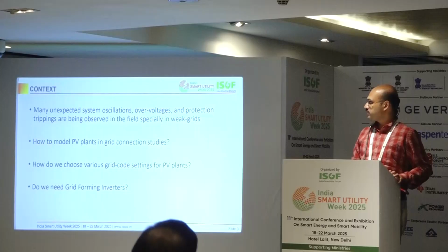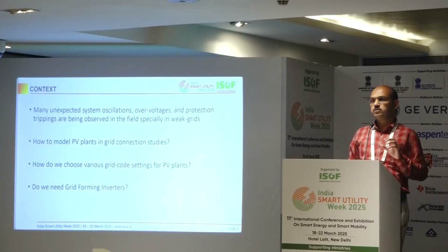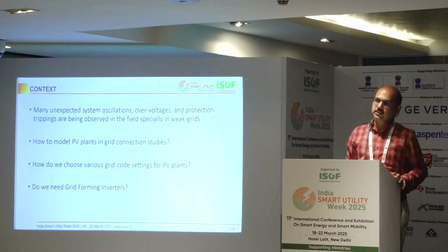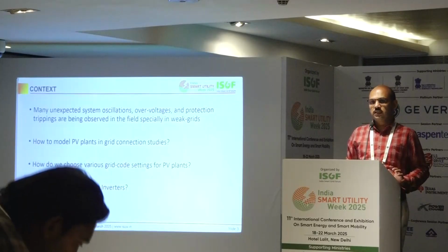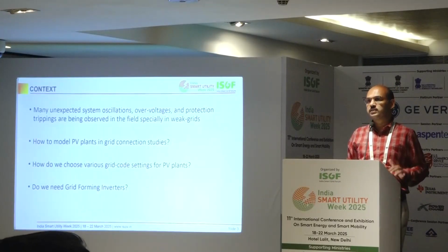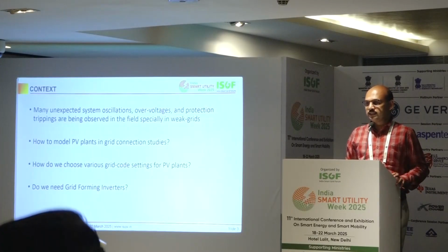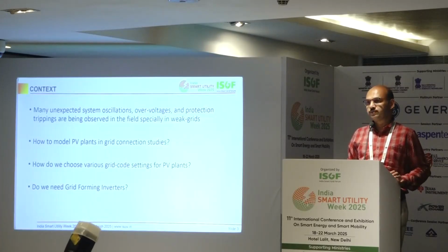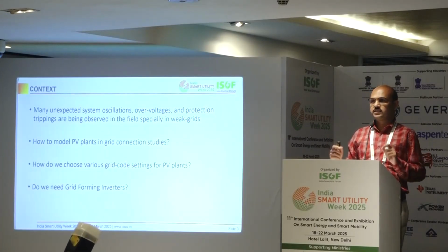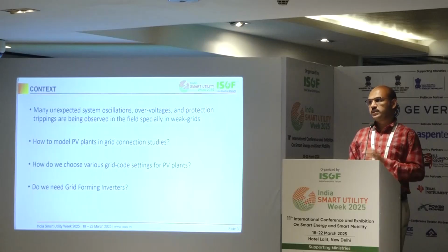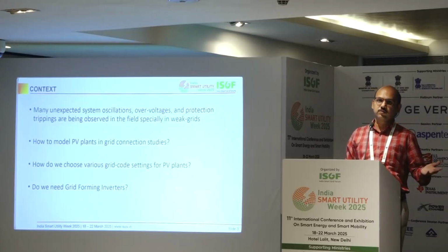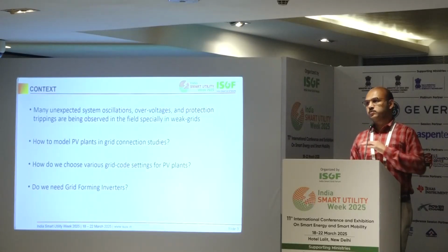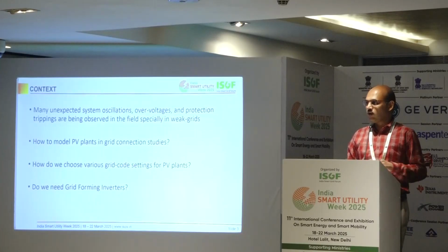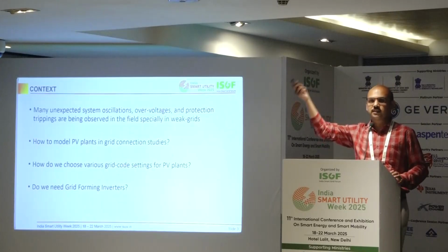Maltripping of protection schemes in the field. So what are the root causes? Till now we really don't have proper models for the inverter which are hardware validated. This is one major issue. The second issue is how to set these grid code settings. Often what we are doing is applying whatever we had for synchronous generators to this case, and often we don't have a clue, so we apply some thumb rule, or we see what others are doing and apply that.